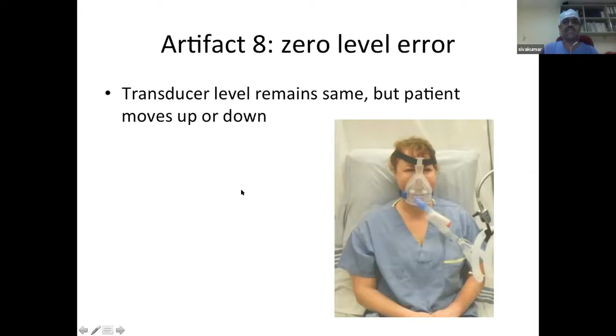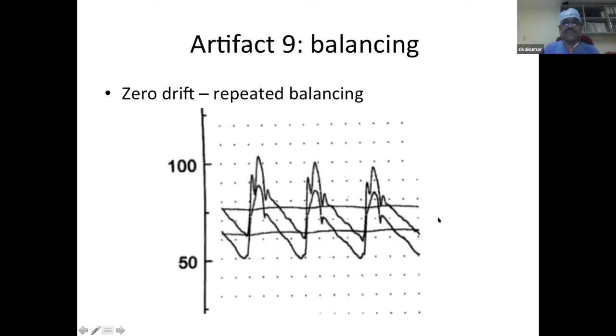What is balancing error? After a short period, we set the balancing so that if there is no pressure at one end, the output is zero. But this keeps drifting, and this zero drift needs rebalancing. So this is zero drift that has occurred, and then you rebalance it back to normal.